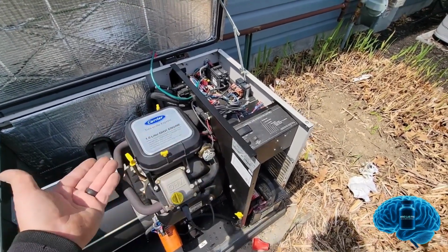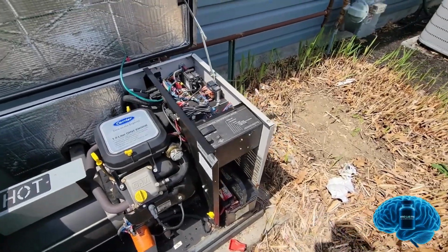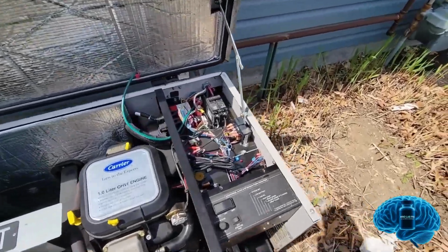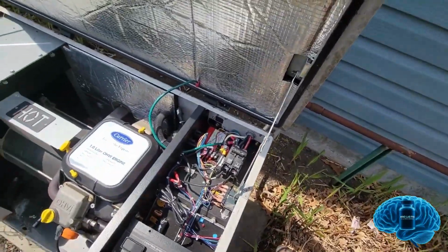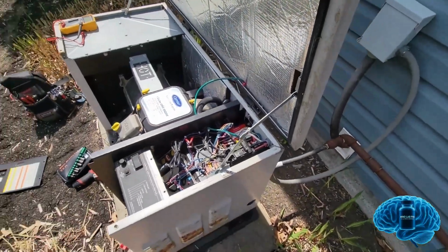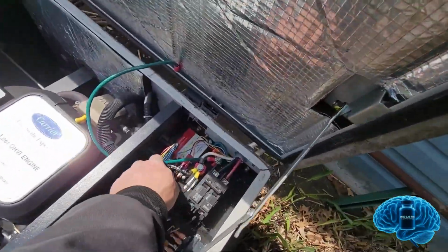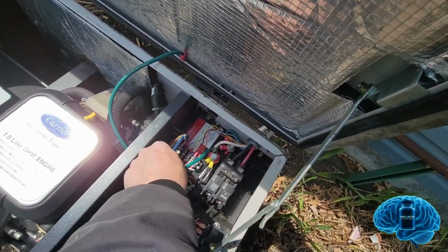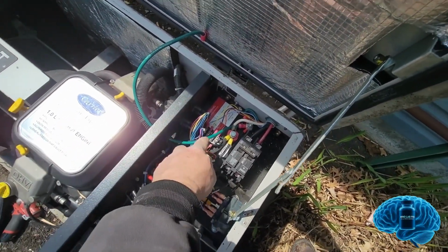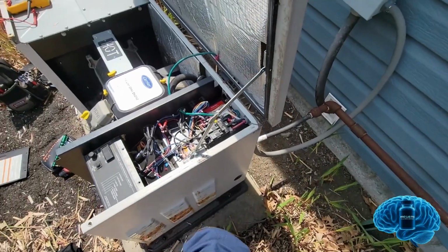The voltage is coming out correctly. Like I said, the only thing we need to do now is test to see if it will transfer over. What we can do is unplug N1 and N2, one of them here, which, like I said, is 230 volts. You're taking a chance of blowing a fuse—those are only rated at about 5 amps.